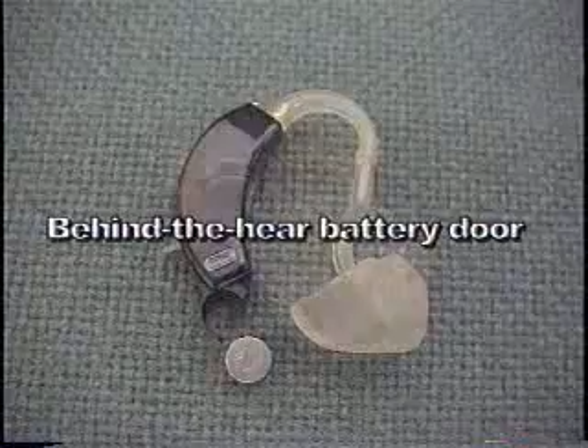It's important that hearing aid batteries are changed every 1 to 2 weeks depending on the style hearing aid an individual has. It's often helpful to work over a towel when changing the battery on a table, so if the battery drops, it doesn't roll. The smaller the hearing aid, the smaller the battery, and the faster that battery will drain. Some hearing aids have warnings that will let an individual know when the hearing aid battery is about to deplete. Other times, the hearing aid will just stop working. One easy way to test this is to hold the hearing aid in your hand and make a fist around the hearing aid. If you hear a whistling sound, then you'll know that the battery is working.